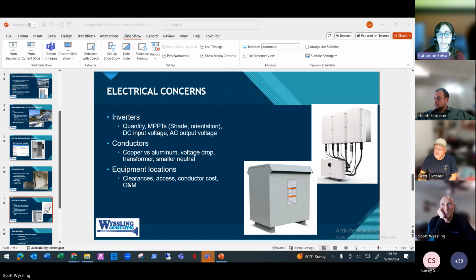Another thing we have to talk about is equipment locations. We have to be very careful with all our clearances. We have to make sure that our AC disconnects are where the fire department and utility company can get to them. And when we're deciding where to put equipment, we also have to look at the conductor cost. Again, if you put your combiners closer or further away, based on whether it's going to be better to run a lot of smaller wires or fewer larger wires, you have to factor that in. And oftentimes just doing a little bit of extra time on the calculations will save you a ton of money in your costs. Another thing to factor in when you're looking at equipment locations is operations and maintenance.